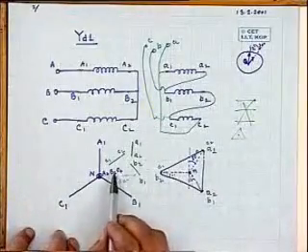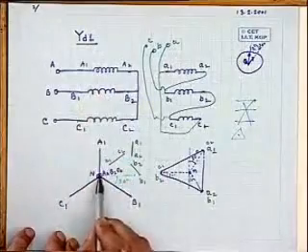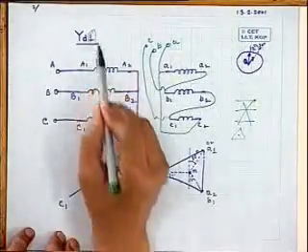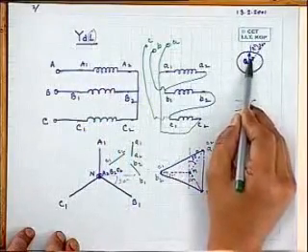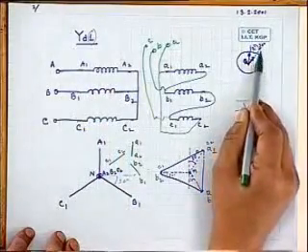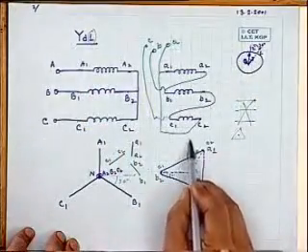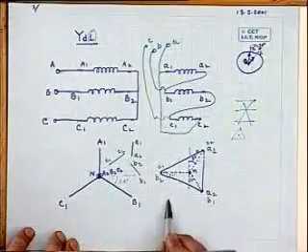Anyway, in this case I have gone step by step. I have to realize the YD1 connection. So what I have done: the A phase diagram I have drawn. Then this has told me that the secondary A phase voltage should lag this by 30 degrees, because this is 1, this clock. So I have drawn a line parallel to this A phase line.